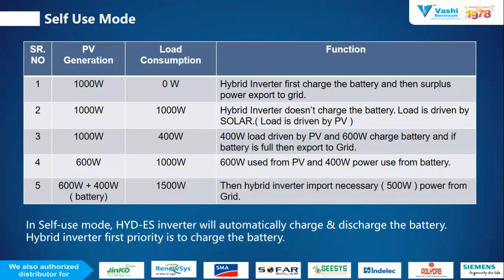So if we consider the PV generation is 1000 watt, and your load consumption is 0 watt, in this condition your PV generation is higher compared to the load consumption. So the hybrid inverter first charges the battery whenever your generation is higher. Our hybrid inverter has first priority to charge the battery. Whenever your battery is charged, you can easily drive the load whenever your PV is not available or your grid is not available. So our first priority is to charge the battery, and if power is surplus, then it will export to the grid. So in the first condition, when PV generation is 1000 watt and load consumption is 0 watt, the hybrid inverter first charges the battery and then the surplus power is exported to the grid.